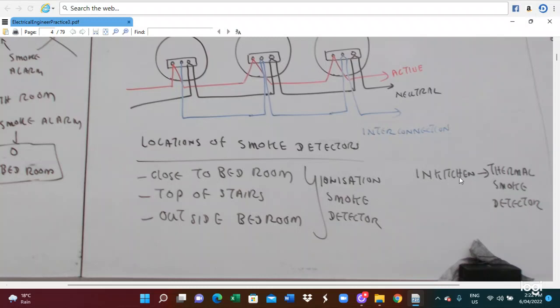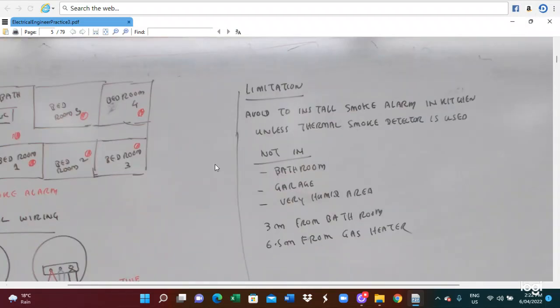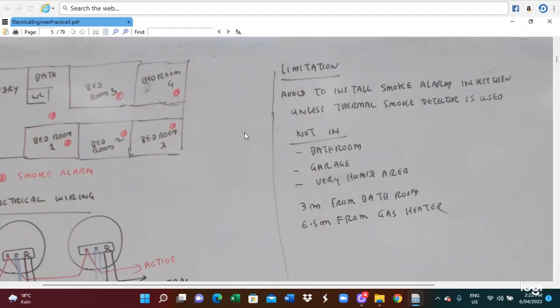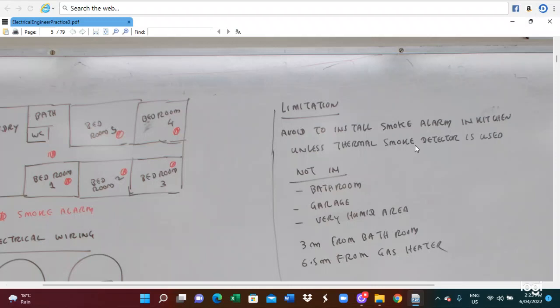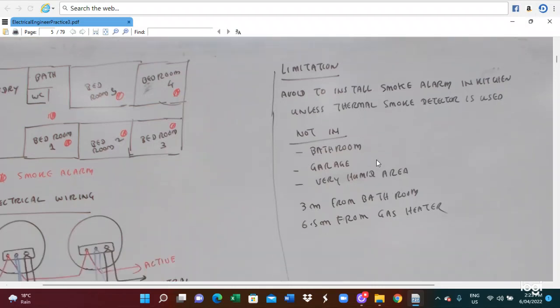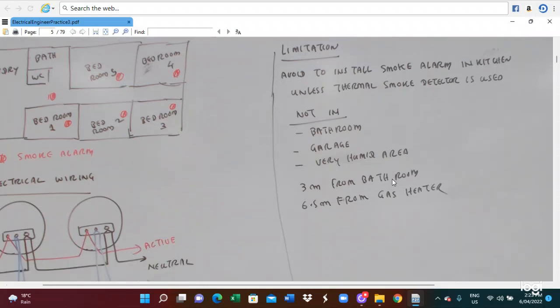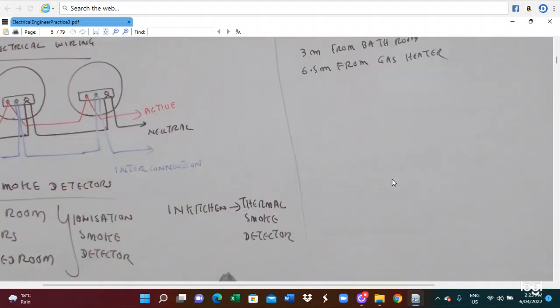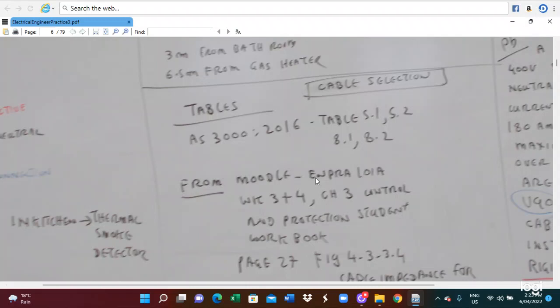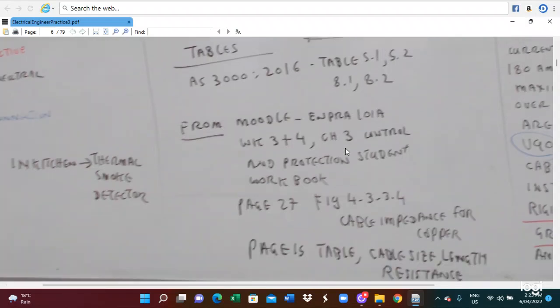In the kitchen, we have to install the thermal smoke detector system. The limitation is to avoid installing the smoke alarm in the kitchen unless a thermal smoke detector is used, not in the bathroom, not in the garage, and not in very humid areas. They must be 3 meters from the bathroom and 6.5 meters from the gas heater. In this case, we have to utilize cable selection. From AS3000 2016, tables 5.1, 5.2, B.1, B.2 have to be utilized.